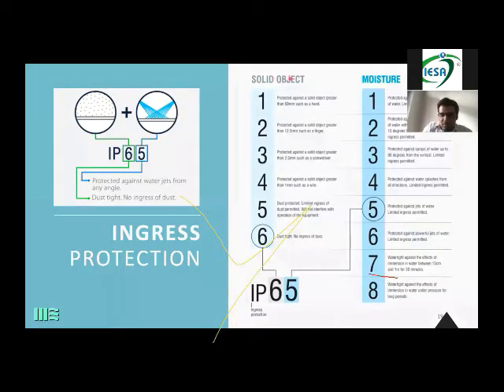So what is the 6? Basically, the first digit refers to solid objects and the other one to moisture. When we say IP6, it means dust tight, no ingress of dust. If it is an outdoor panel, or indoor also, dust can't enter the electrical equipment because it is not good for electrical circuits or any live wires. So the material has to be IP6. Now comes 5. If it is IP65, it is dust tight, and 5 means it is protected against jets of water, limited ingress permitted. Very important point when dealing with outdoor or indoor events.